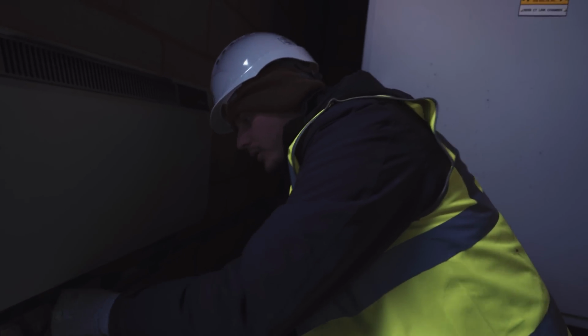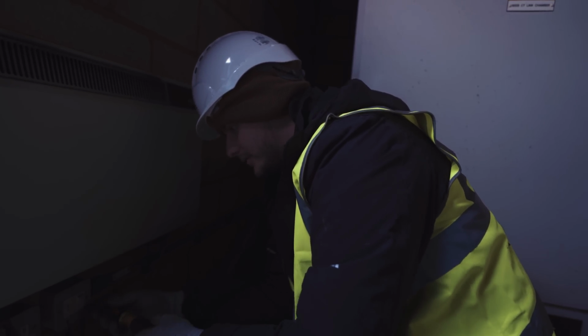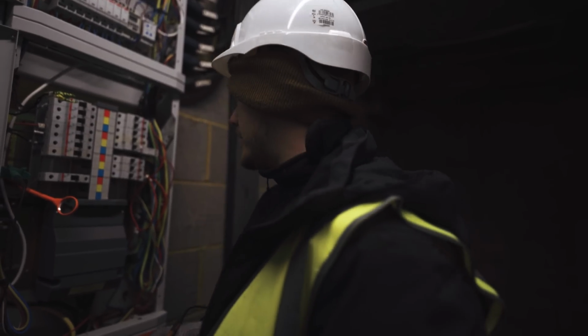Like I say, 2 more circuits to do, and then it's just insulation resistance, and I've just made some notes basically on stuff that doesn't make sense or where it got mapped out before, just judging on what lights come on basically of the contactors and stuff. Some of the circuit references are a little bit wrong, so get all that wrapped up and that will be it.